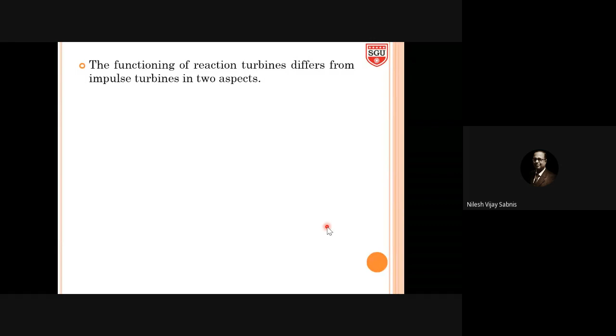The function of a reaction turbine differs from the impulse turbine in two ways. This point is important. In an impulse turbine, the available potential energy is completely converted to kinetic energy by the nozzle before the water enters the runner. Overall energy is converted into kinetic energy. Pressure in the runner is constant and it is atmospheric, because the turbine casing is not airtight. Whatever atmospheric pressure is there, that is constant around the turbine runner.